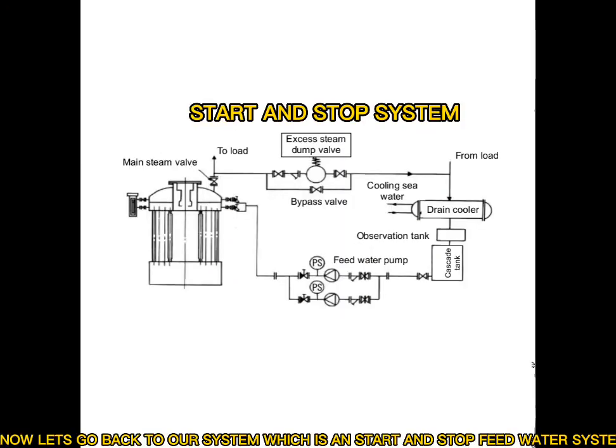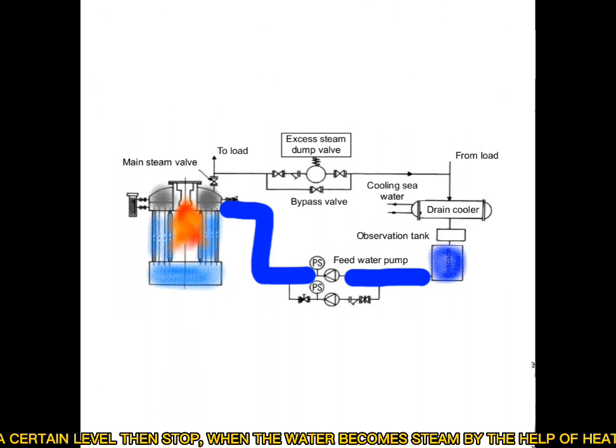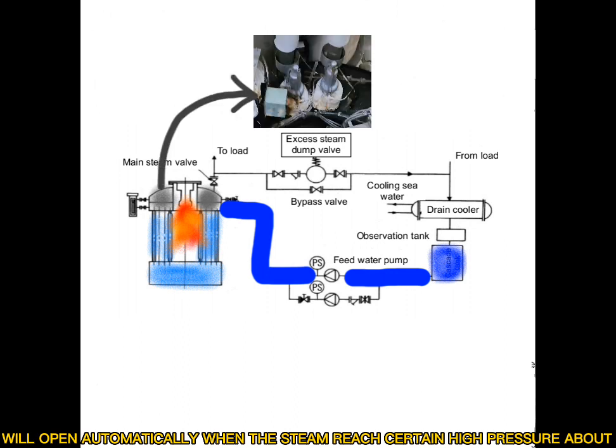In the start-and-stop feed water system, water flows from the cascade tank, is suctioned by the feed water pump, and delivered to the boiler water drum. At a certain level, the pump stops. When the water becomes steam by the help of heating mediums — the main burner and the exhaust gas economizer from the main engine — the boiler also has a safety valve attached. This valve will open automatically when steam reaches a certain high pressure of around 0.7 megapascal or more, to protect the equipment from overpressure.